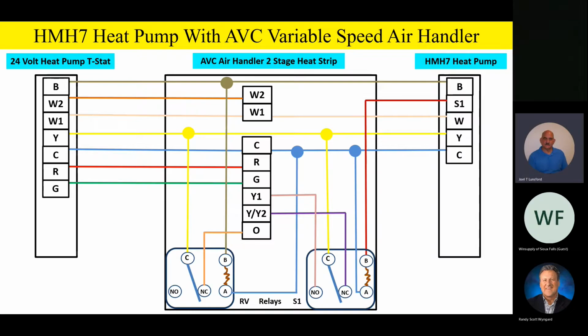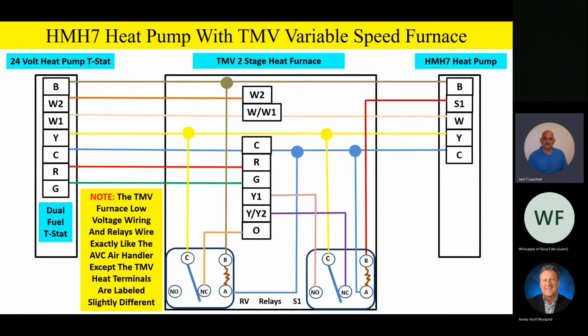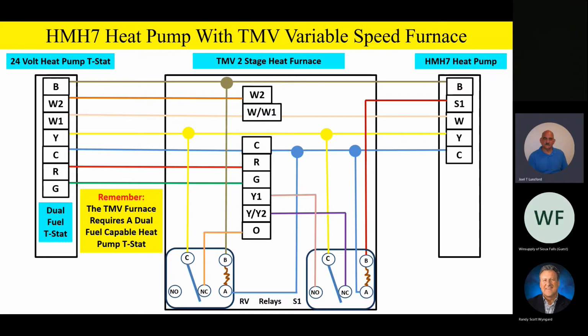On the TMV furnace, the TMV is a two-stage variable speed furnace. Fellas, it wires exactly like the AVC air handler. It wires exactly like a variable speed air handler. The only difference is the terminal designation is slightly different. We have a W2 terminal and a W/W1 terminal on the furnace. Other than that, it wires exactly the same as far as the switching relays, the RV relay, the whole nine yards. So please remember one more time that TMV furnace has to have a dual fuel capable heat pump thermostat on the wall for proper operation.